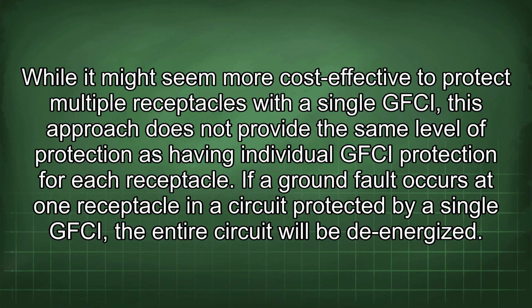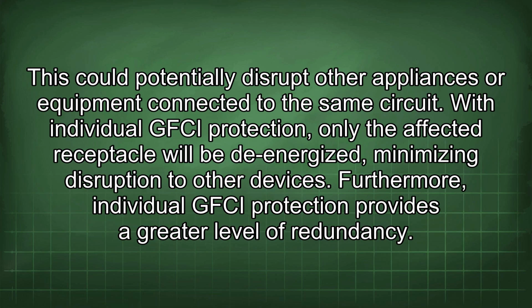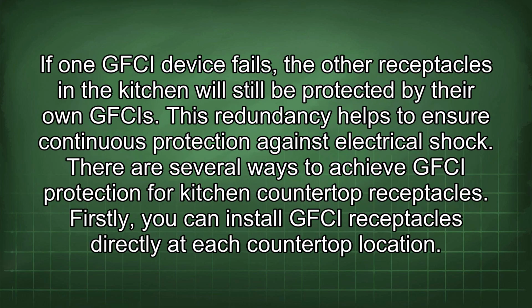If a ground fault occurs at one receptacle in a circuit protected by a single GFCI, the entire circuit will be de-energized. This could potentially disrupt other appliances or equipment connected to the same circuit. With individual GFCI protection, only the affected receptacle will be de-energized, minimizing disruption to other devices. Furthermore, individual GFCI protection provides a greater level of redundancy. If one GFCI device fails, the other receptacles in the kitchen will still be protected by their own GFCIs. This redundancy helps to ensure continuous protection against electrical shock.